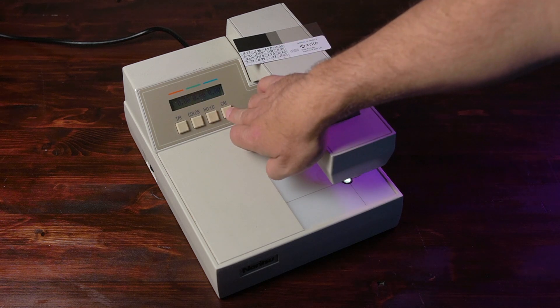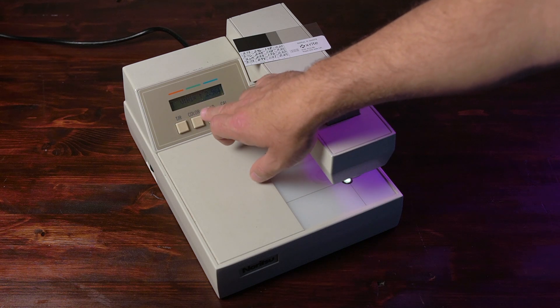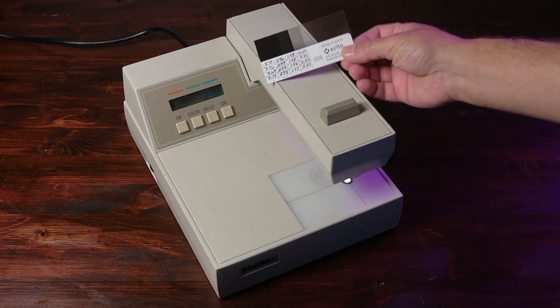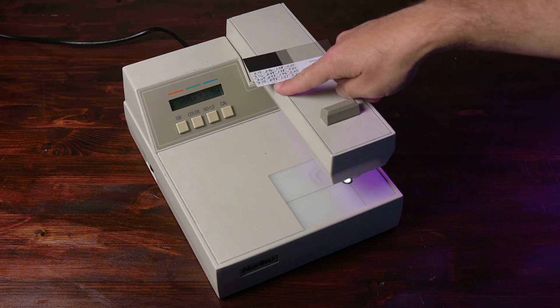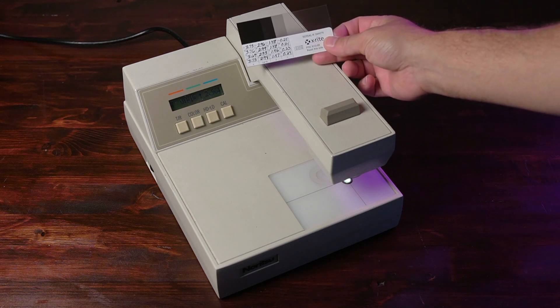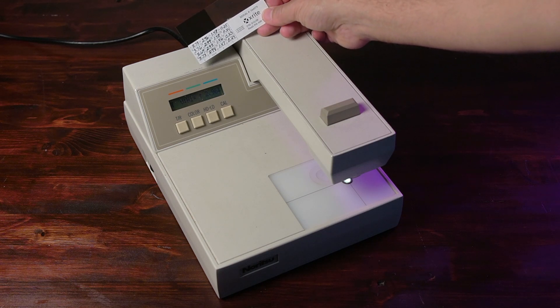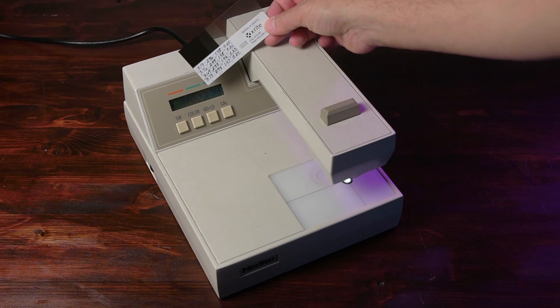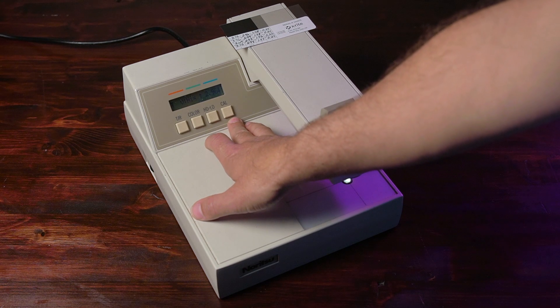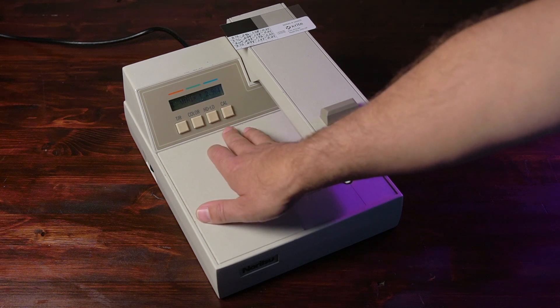To begin the calibration, hit Cal twice. It's now saying visual high and I have a value of 2.96. Looking at my card, I have Cal high and my visual is 2.96. If it did not display that on the machine, I would need to change the values. I would change them by either pushing HOLD to go down and Cal to go up, or the other way around — HOLD goes up, Cal goes down.